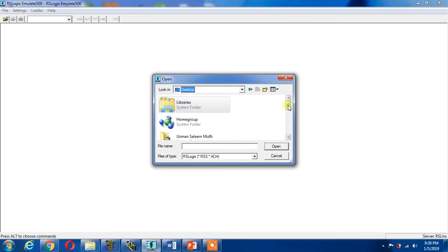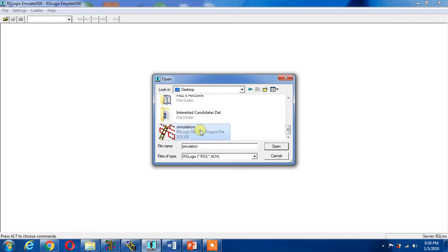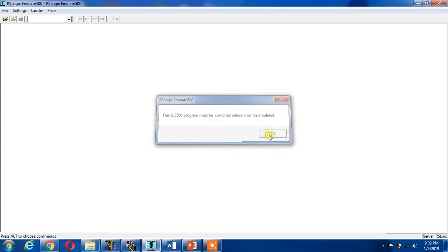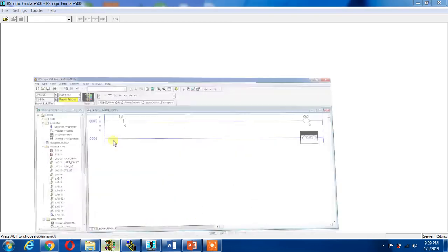But there is some problem which I will find when I open this file in emulator. I open it, it will give me an error: this SLC500 program must be compiled before it can be emulated. OK, I can go to my program and compile it.